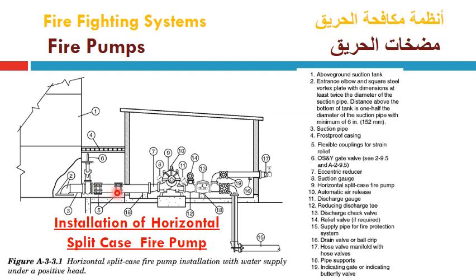We can use one or two flexible couplings to be located somewhere here to install the valve easily between these two fixed dimensions of the wall, which have been designed in concrete. Then number 6, OS and Y gate valve, which will be located here with a rising stem, showing that the valve is in open position.